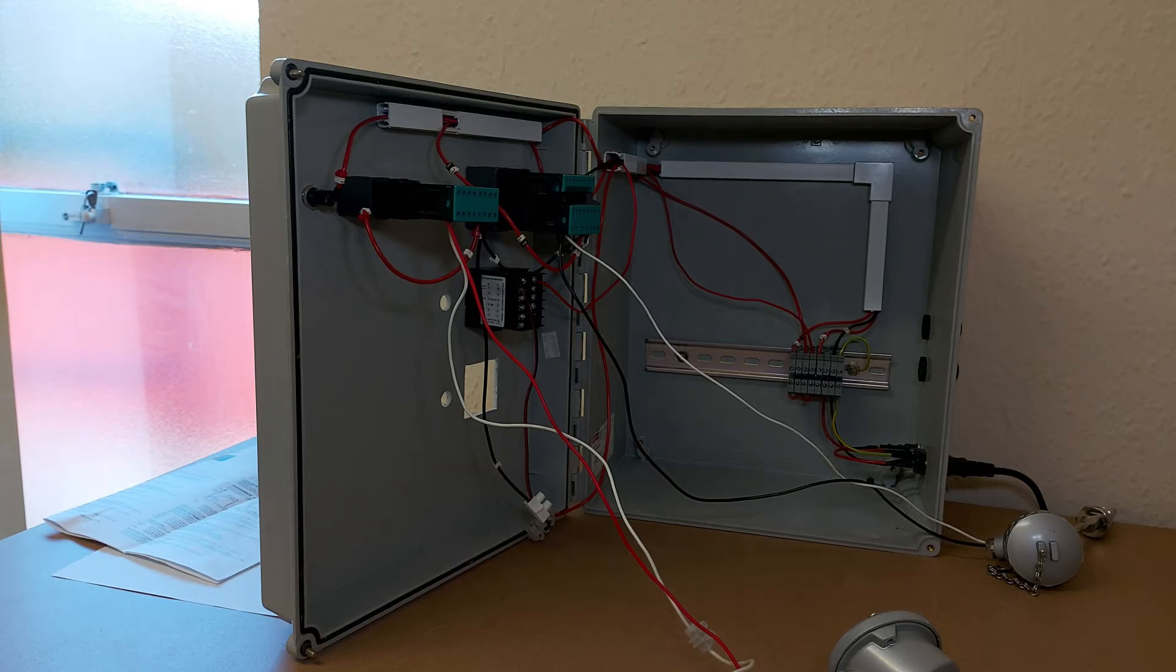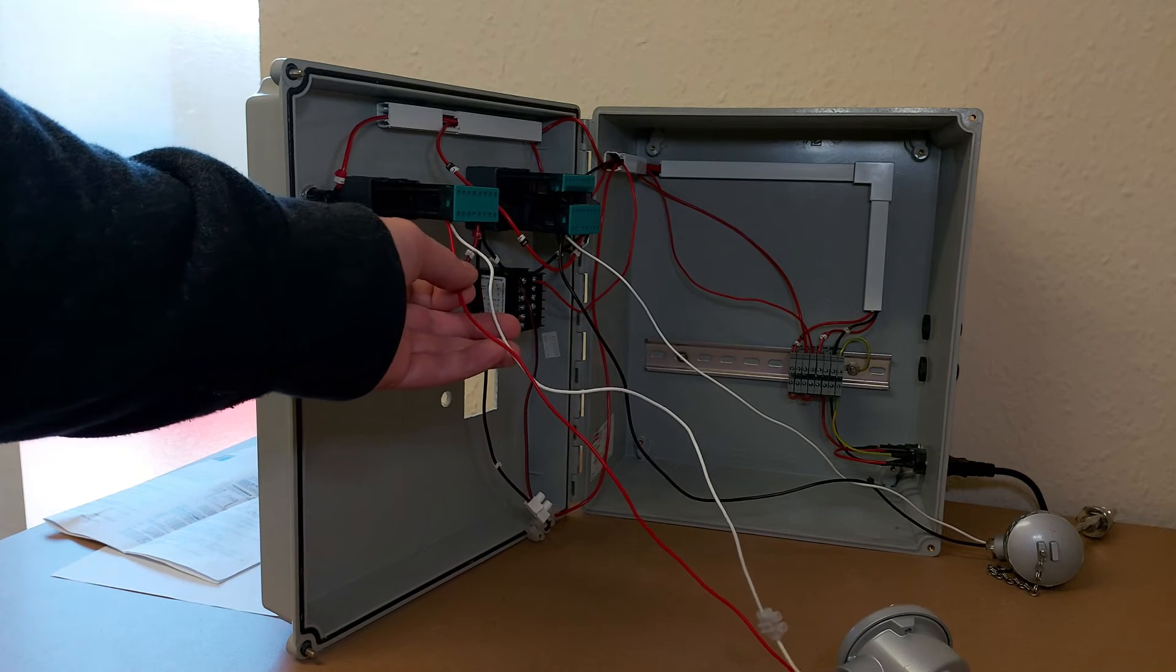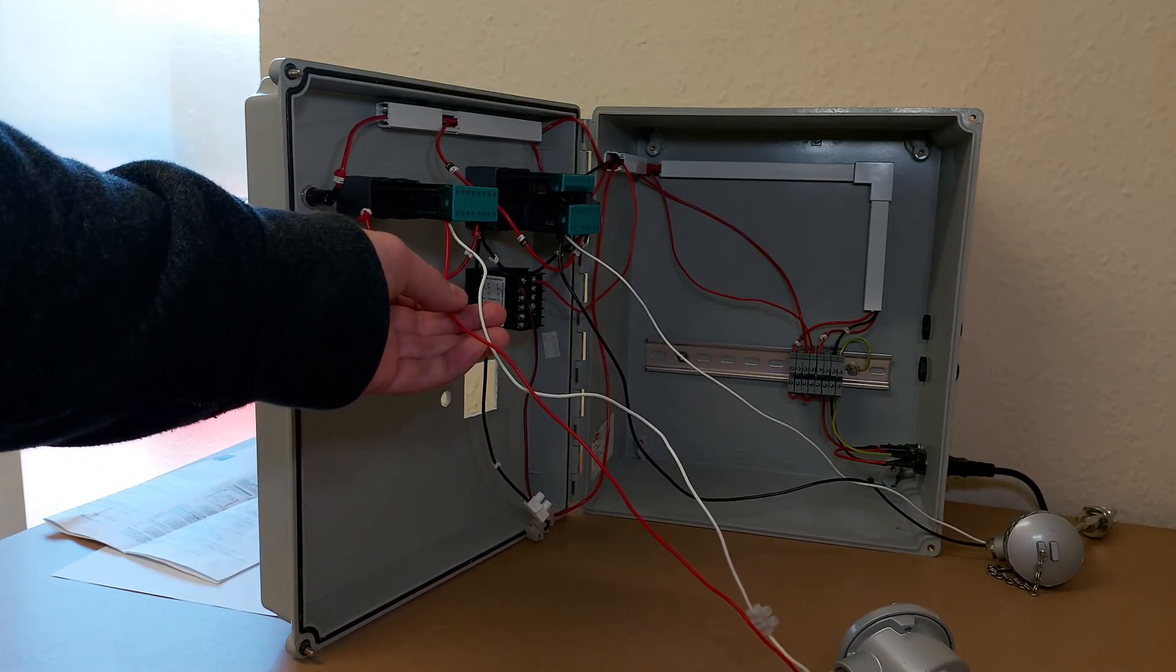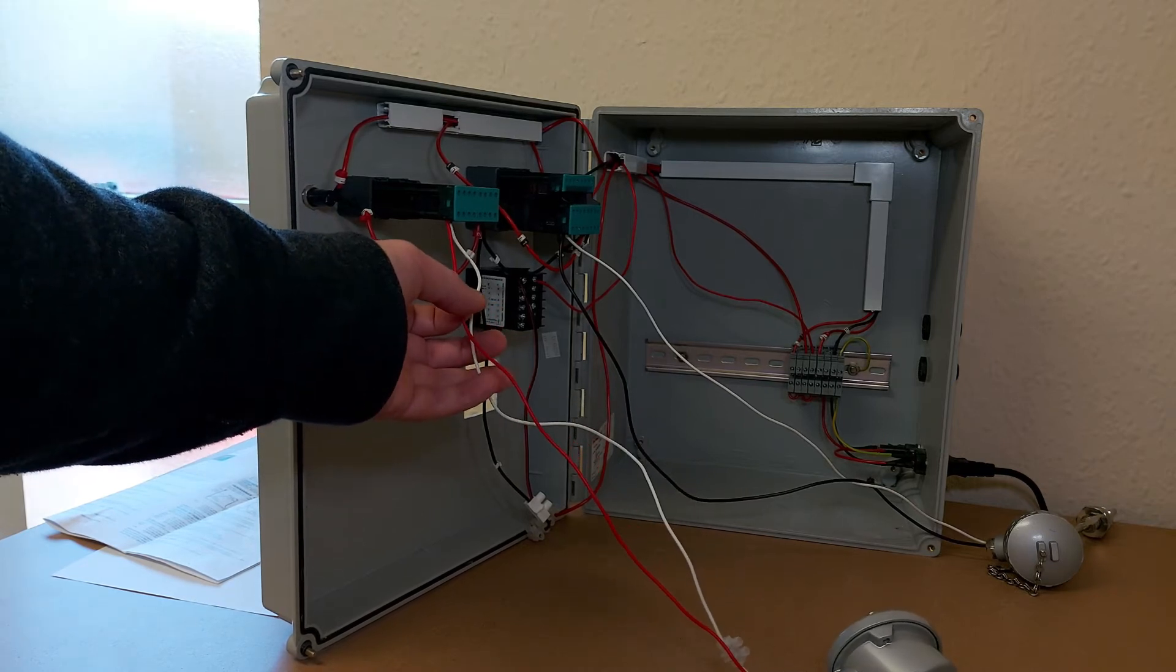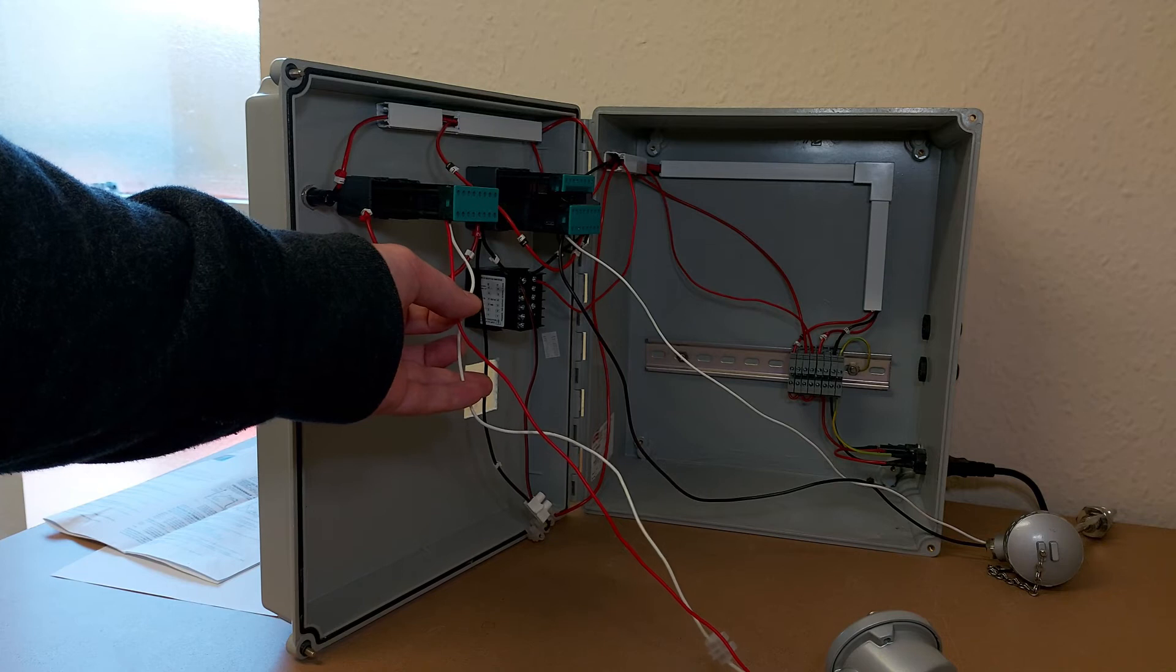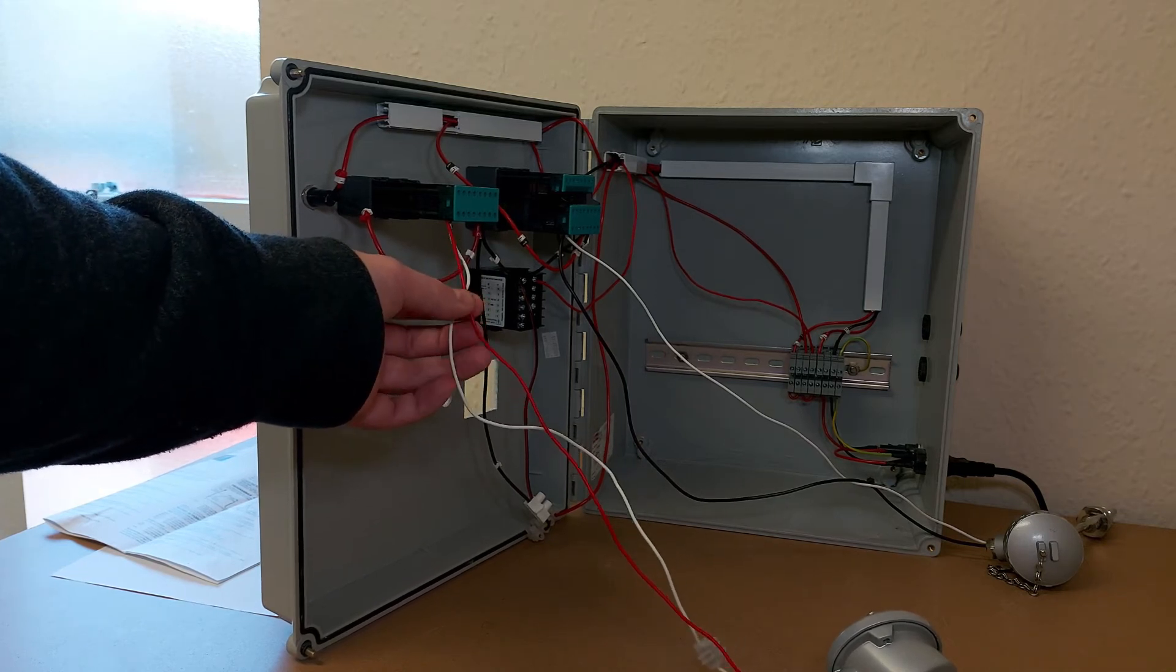Here I have a two-wire PT100. If you have a three-wire PT100 sensor, you will have one white wire and two red wires. Connect it to the controller as you can see here with the CAL3300.